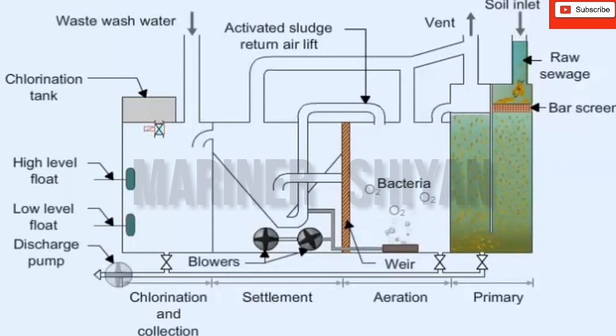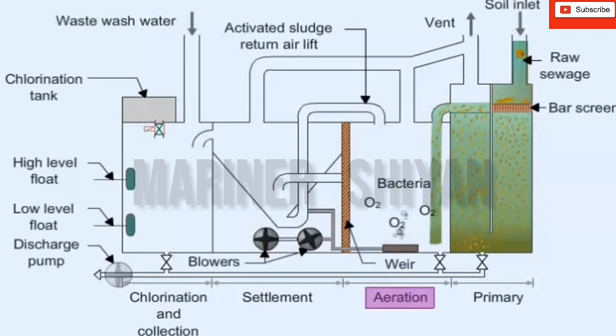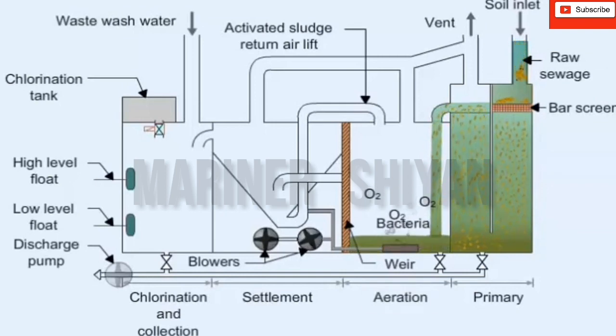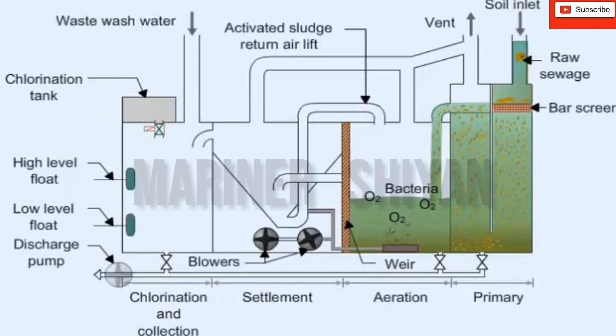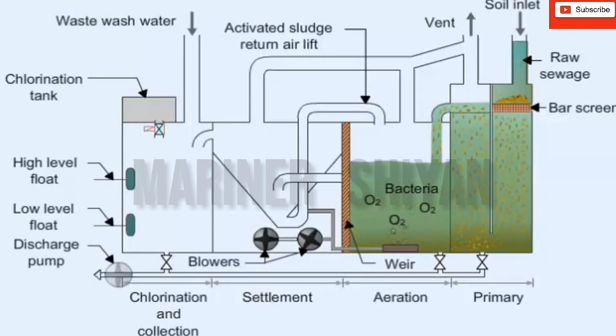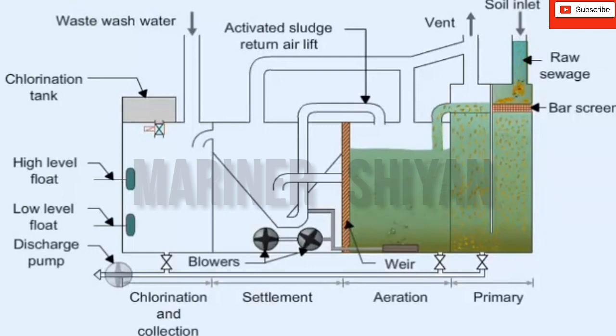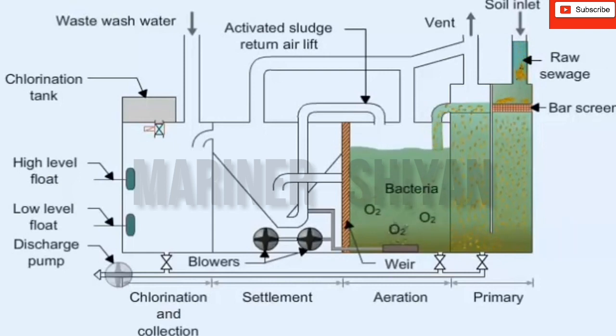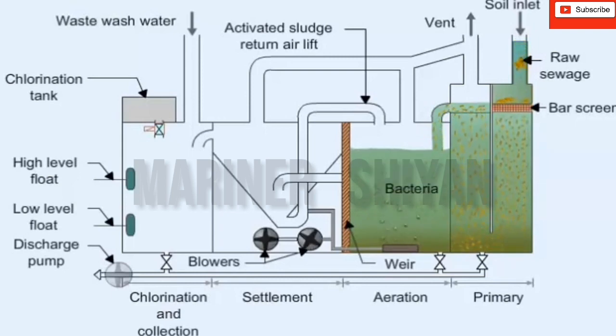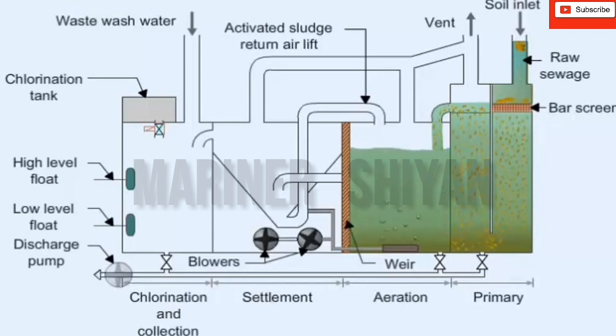Breakdown of the waste in the aeration compartment is induced by bacteriological organisms promoted by the presence of oxygen. The oxygen is supplied by air from the blowers, which enters the aeration section through a fine bubble diffuser at the bottom. The diffuser is of porous material, so clean air is needed to prevent blockage. The bubbles, besides providing oxygen, also create turbulence so that settlement is prevented and good mixing is obtained.